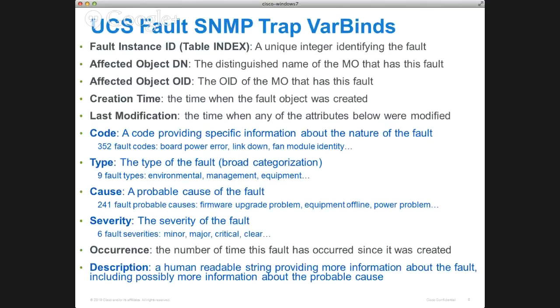And then we have a lot of other things like the fault code, and that's the actual F0000 number, where zeros can be any integer, that defines the appropriate faults in a particular system. So I mentioned like 350 fault codes. Those are the fault codes that I would recommend you monitor. There's 1,400 faults. There's a lot of different faults.